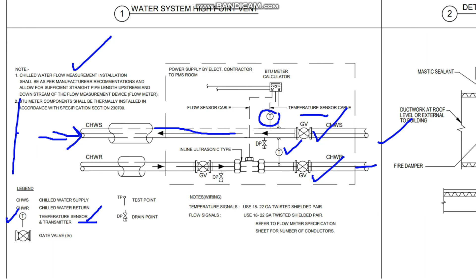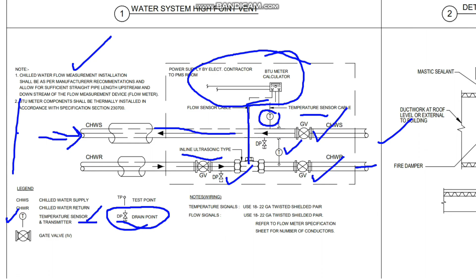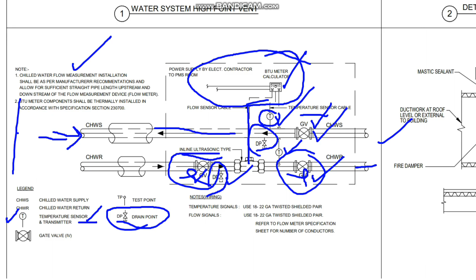Like you see here, we have the BTU meter calculator. We have the connection from here, and after that we have the drain point. DP means drain point, to drain the water. Then we have the isolation valve again. In this line we can see there are two isolation valves, front and back side of this arrangement, because if you want to do any maintenance at this level, we can close these two isolation valves for the maintenance. The third isolation valve we have in this supply line. After that we have two drain points in the supply and return line. Then we have the temperature sensor and transmitter in the line. These are the important accessories we have to consider for the BTU meter.